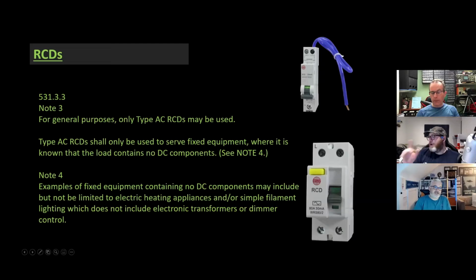So that's just a question on this AC one. We've hinted that in the future we might have to look at EICRs when we find an installation with an AC RCD. The equipment that's there at the time might now warrant consideration for a C2, potentially - if that equipment is definitely blinding and impacting the effectiveness of the RCD, making it redundant.